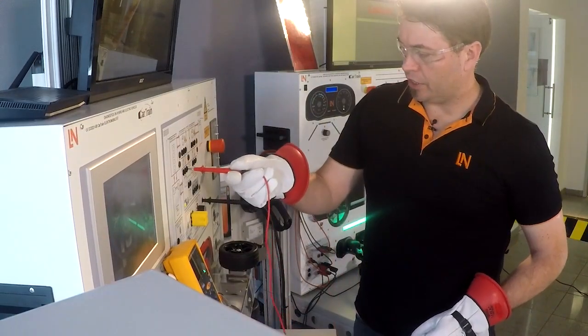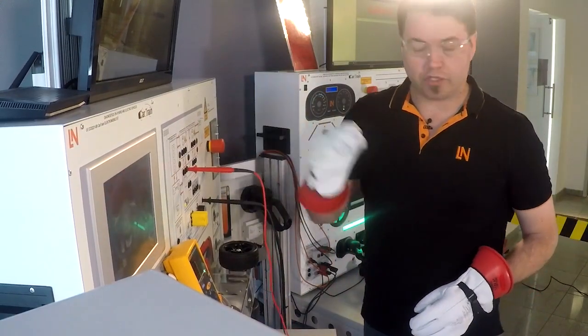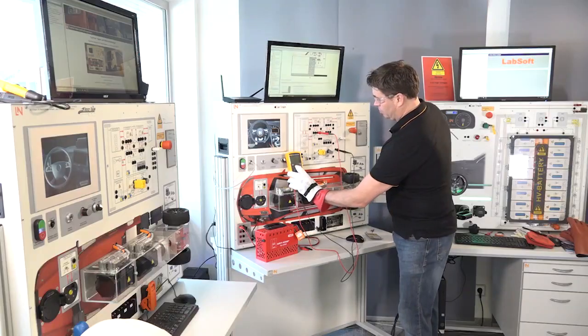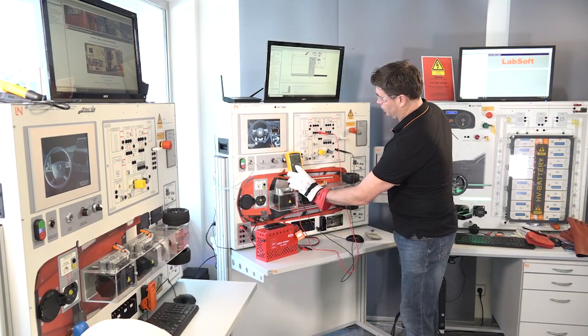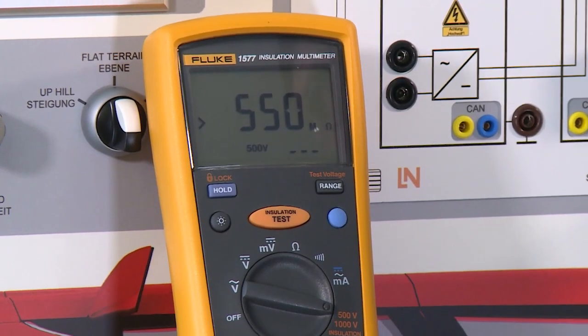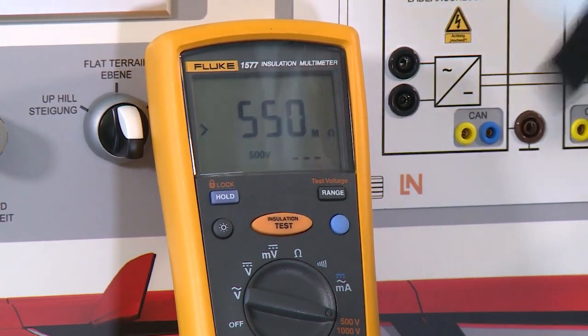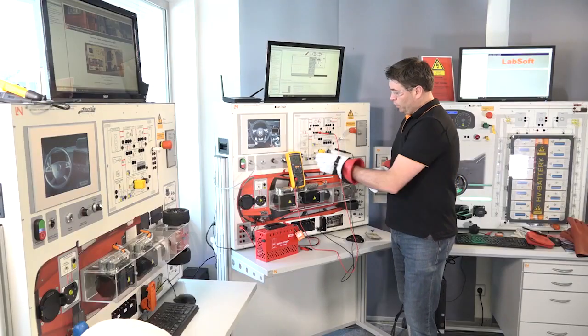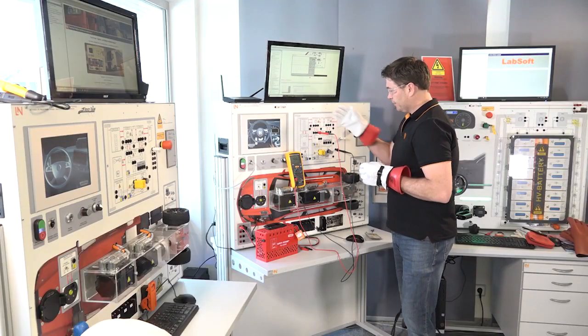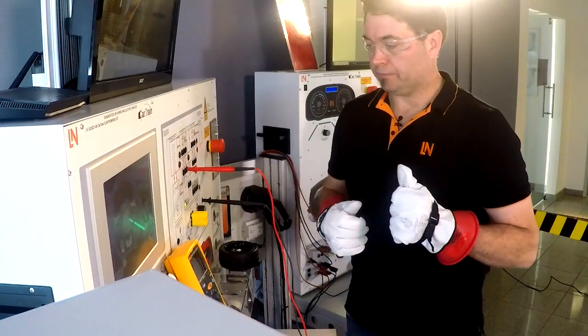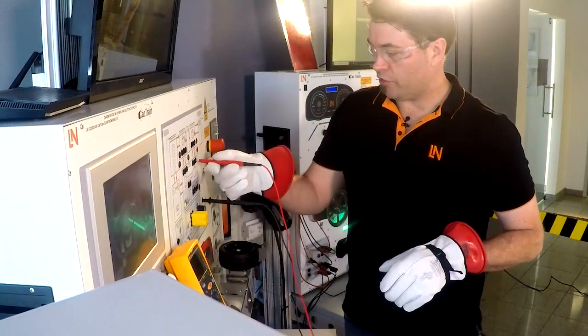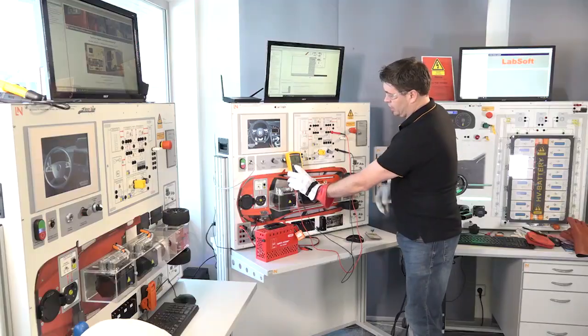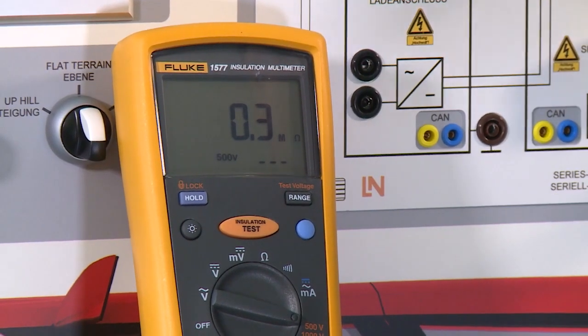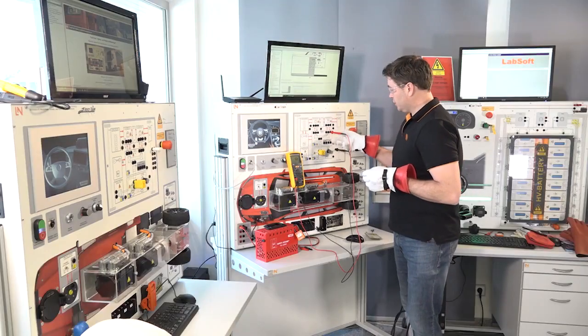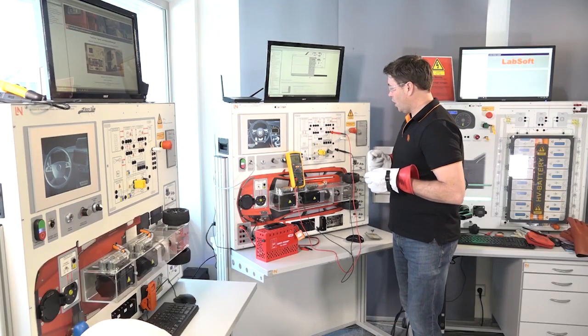Because we don't know exactly which motor generator has the fault, we're going to start on motor generator 1. So simply by doing the insulation test, we can see here 550 mega ohms. That's done at 500 volts, so it's actually doing a real insulation test. We can see with this result that motor generator 1 is perfect. So we'll go to motor generator 2 now, and you can see in this case 0.3 mega ohms, that's well under the limit for a correct insulation test. So we can see now that the fault lies within motor generator 2.